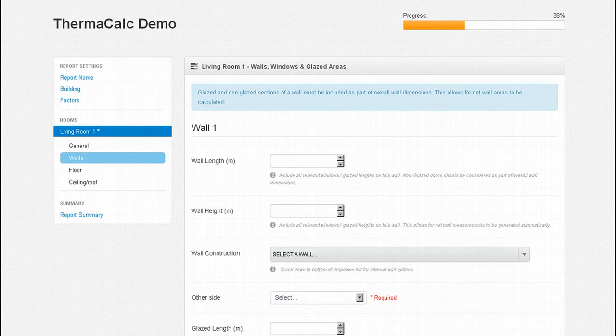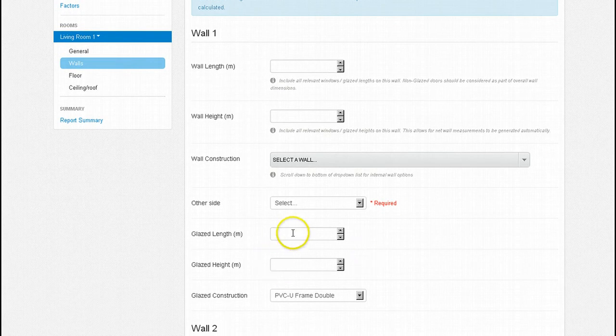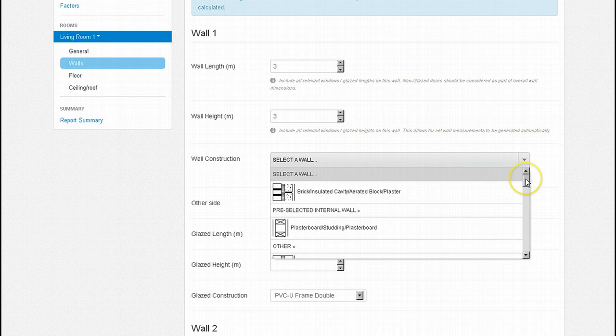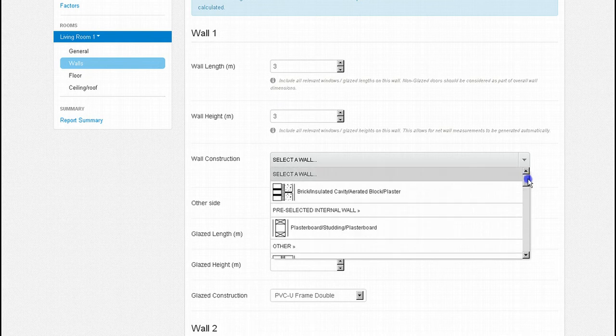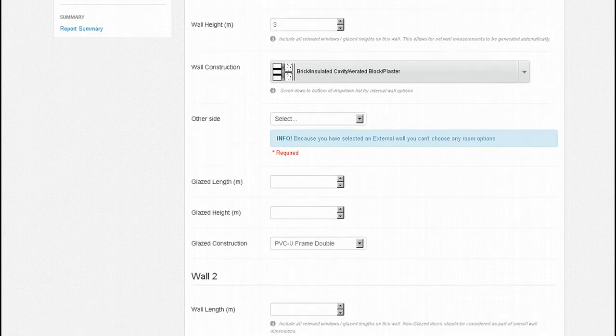Total wall lengths and widths are typed into their relevant fields. Window measurements are placed in the glazing fields beneath. Separating the two in this way allows the system to work out the net wall dimensions. If a wall is completely glazed such as those found in a conservatory, basement or extension, place your measurements in the glazed length and width fields. Wall 1 is 3 metres long and 3 metres high. If you scroll down the wall construction tab you will see our 2 pre-selected external and internal walls from earlier at the top of the list, as well as the other 22 wall options beneath. Wall 1 is our pre-selected external brick insulated cavity aerated block and plaster wall at the top, so we select that.